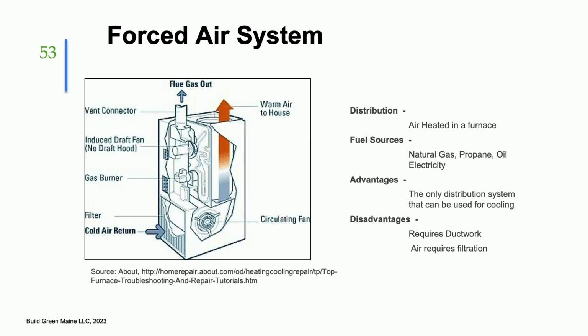Disadvantages for forced hot air system. It requires ductwork, which is not a DIY thing. You need someone to design that forced hot air system. I am shocked and amazed every time I come into a basement and see that the ductwork is actually insulated. Most of the time it is not. So you have a lot of heat loss in a basement. So if you guys ever come into a house with ductwork in the basement and the basement is unfinished, then that's definitely a big recommendation you want to make to get those ducts insulated, because otherwise it's just heating the basement. Why are you heating the basement?